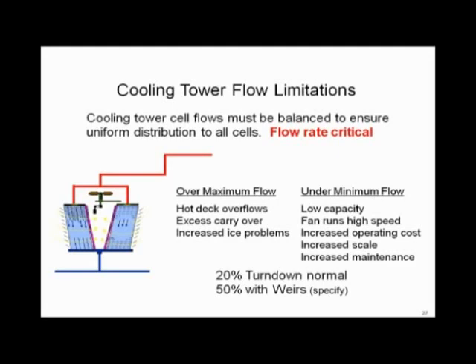In cold weather, if you exceed the tower's capacity to handle flow on the max side, it's going to freeze up. On the low side, is there a minimum allowable flow? The answer is also yes.